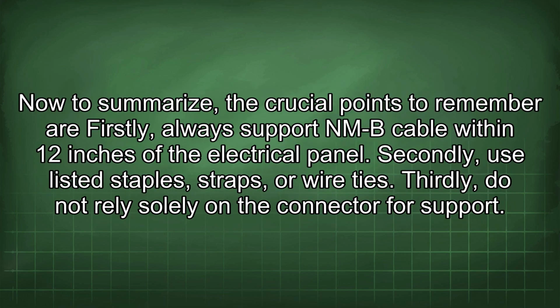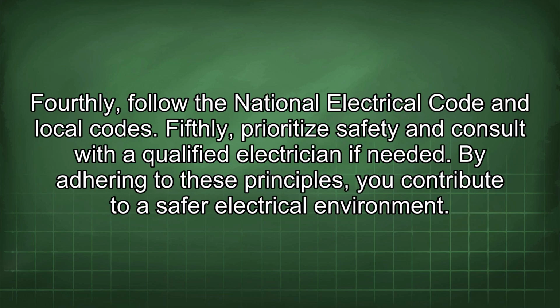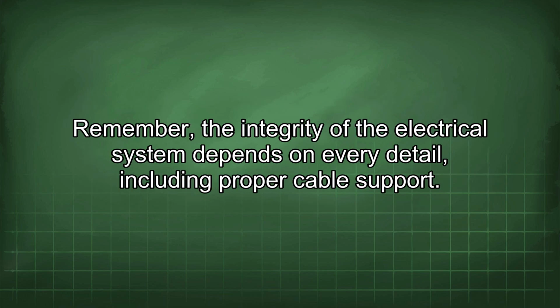Now to summarize, the crucial points to remember are: firstly, always support an NMB cable within 12 inches of the electrical panel. Secondly, use listed staples, straps, or wire ties. Thirdly, do not rely solely on the connector for support. Fourthly, follow the National Electrical Code and local codes. Fifthly, prioritize safety and consult with a qualified electrician if needed. By adhering to these principles, you contribute to a safer electrical environment. Remember, the integrity of the electrical system depends on every detail, including proper cable support.